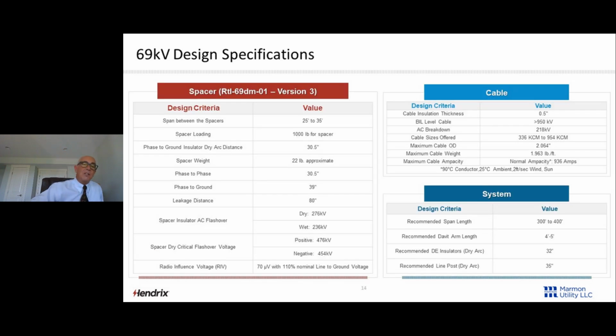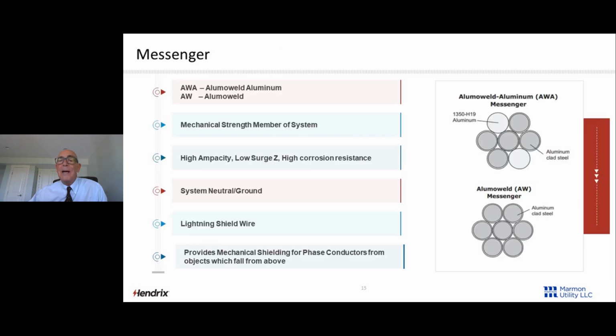Our design specs, we'll talk about the spacer in a minute. The cable, again, we've got a close over 950 kV BIL, 218 kV AC breakdown, all kinds of good things with that conductor. So the messenger is the same messenger that we're using at lower voltages. It's AWA, Alumoweld aluminum, or AW, Alumoweld. It's the mechanical strength messenger member of the system. Again, it holds everything up.